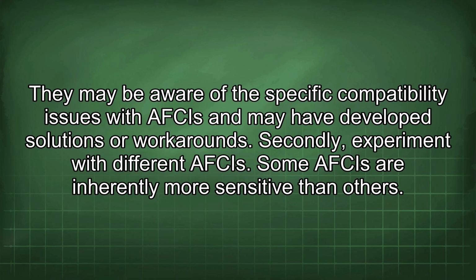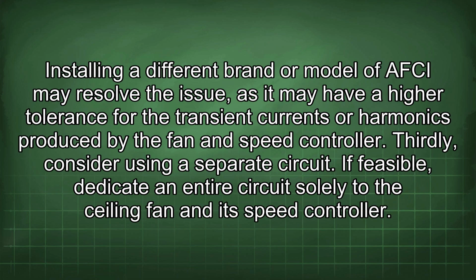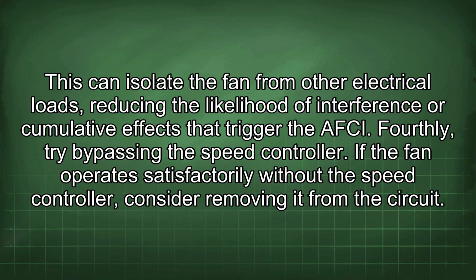Secondly, experiment with different AFCIs. Some AFCIs are inherently more sensitive than others. Installing a different brand or model of AFCI may resolve the issue, as it may have a higher tolerance for the transient currents or harmonics produced by the fan and speed controller. Thirdly, consider using a separate circuit. If feasible, dedicate an entire circuit solely to the ceiling fan and its speed controller. This can isolate the fan from other electrical loads, reducing the likelihood of interference or cumulative effects that trigger the AFCI.